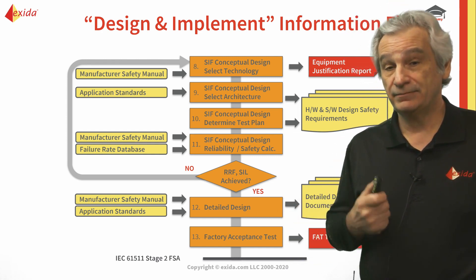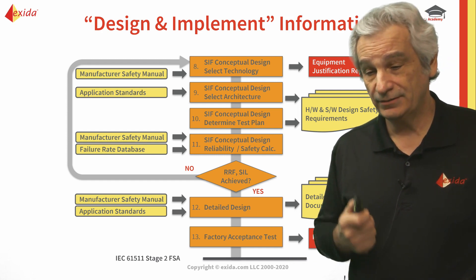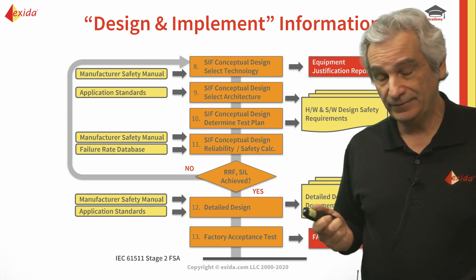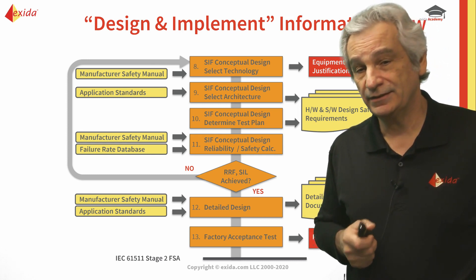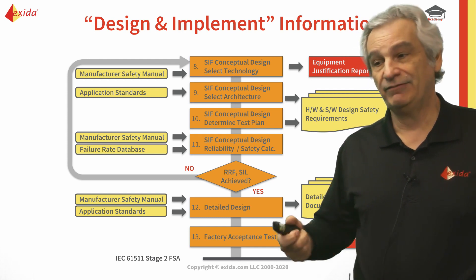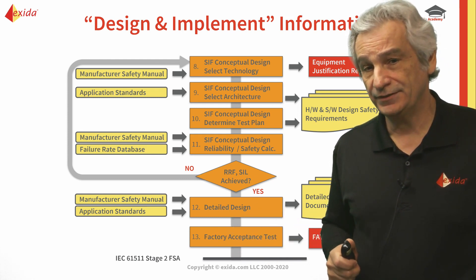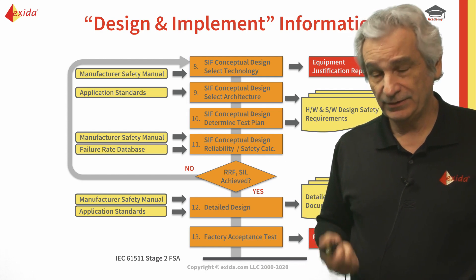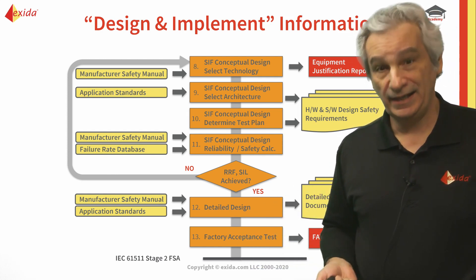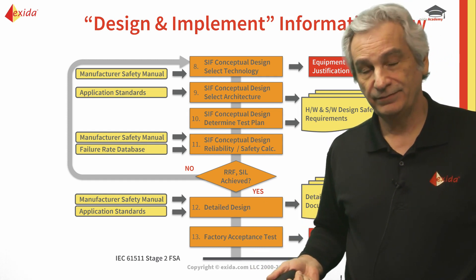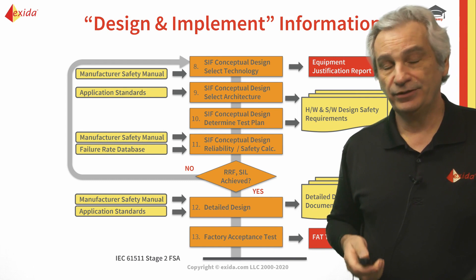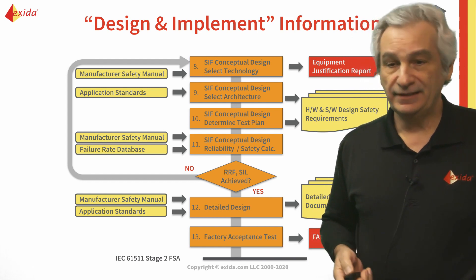The third element is systematic capability, which is very important. We've had clients ask us to do SIL verification but ignore the systematic because they haven't used certified devices. We say: in order to do this, you have to give us a written reason why we should ignore the systematic, because it is a requirement if you're going to meet IEC 61511.